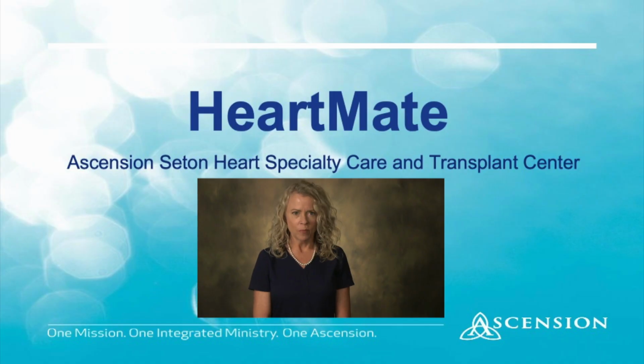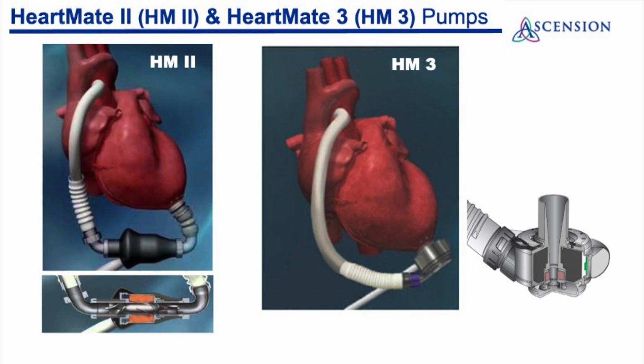First, I'm going to cover HeartMate devices. Despite the design difference, both pump motors contain magnets, and when electricity is applied, the motor spins to pull blood out of the ventricle. The faster the motor speed, the higher the flow of blood out of the ventricle and into circulation. Remember, flow is continuous, so depending on the degree of support, the patient may or may not have a pulse. The motor speed is determined based on the patient's need when the VAD is implanted.